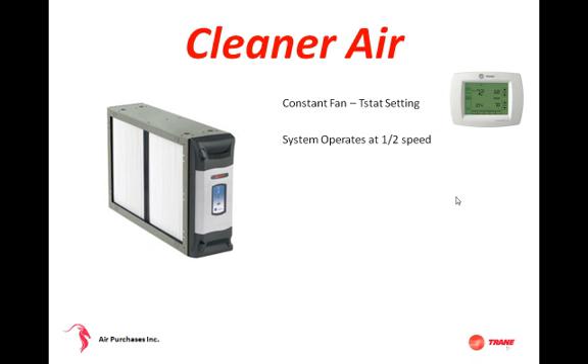Now with Trane variable speed on constant fan, our system operates at half speed. So our blower, based on a 3-ton 1200 CFM system, operates at 600 CFM on constant fan, or half the speed, removing more airborne particulates, because as we move that air slower across the media, we're going to take out more particles from the air.